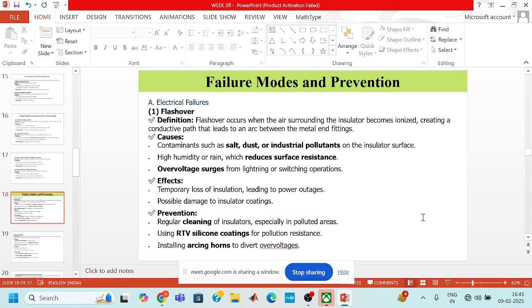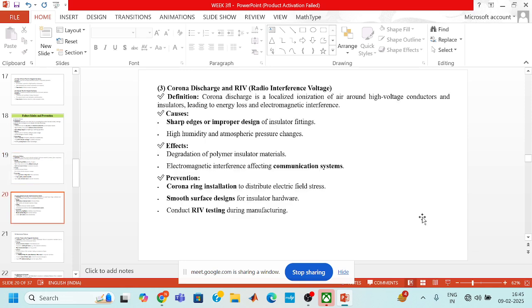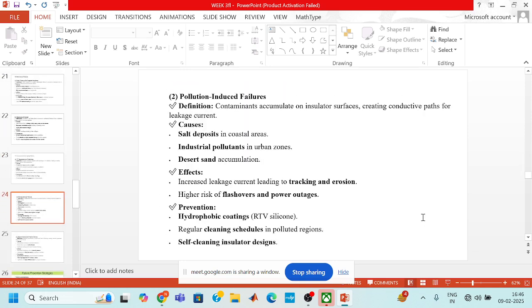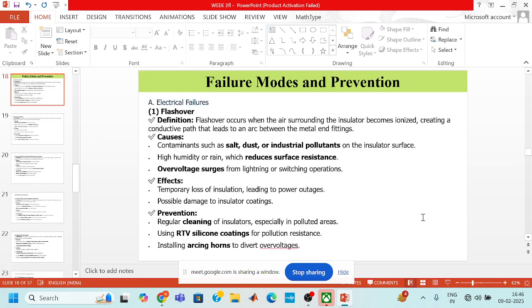Sorry. So now moving on to the failure modes and prevention. There are some failures like electrical failures, puncture failures, corona discharge, mechanical failures, and environmental failures. Okay, so among electrical failures, there is flashover. Flashover occurs when the air surrounding the insulators becomes ionized, and it creates a conductive path that leads to an arc between the metal fittings. Flashover is caused by contaminants such as salt, dust, or industrial pollutants on the insulator surface, and high humidity or rain, which reduces surface resistance.